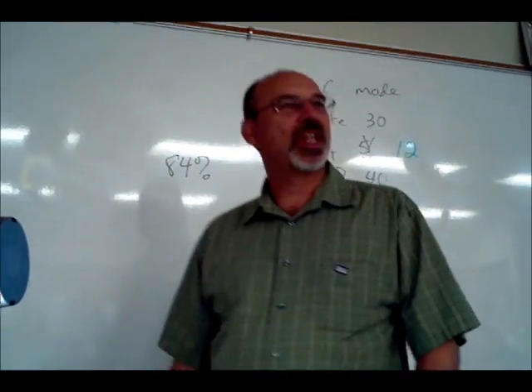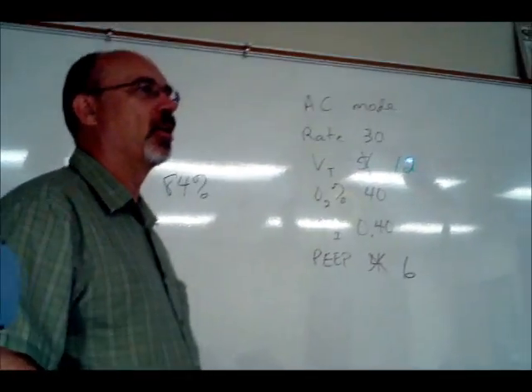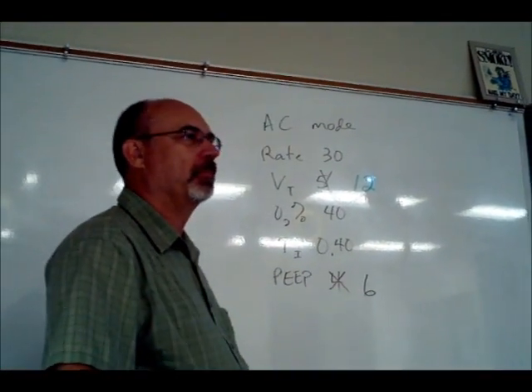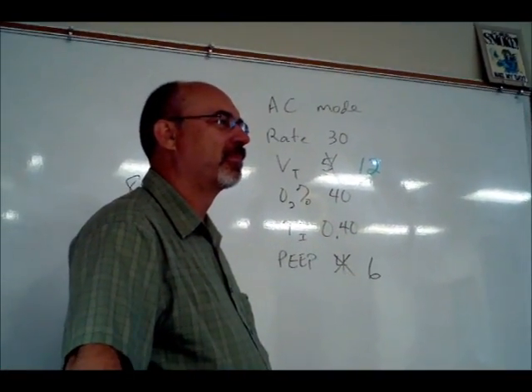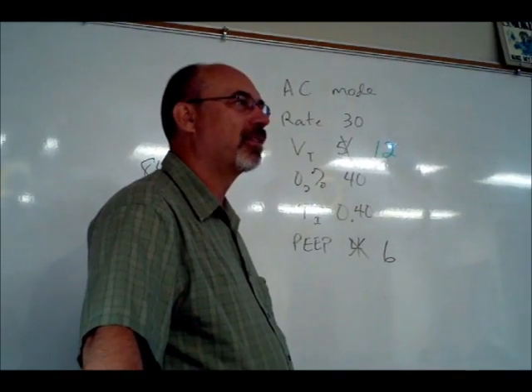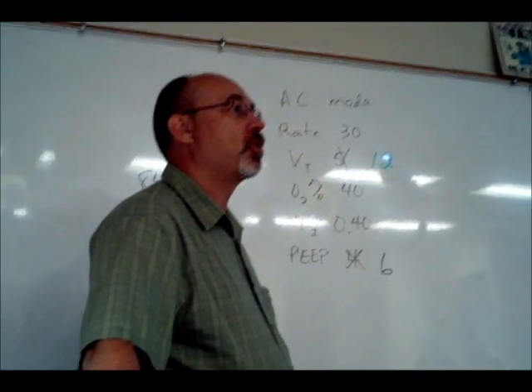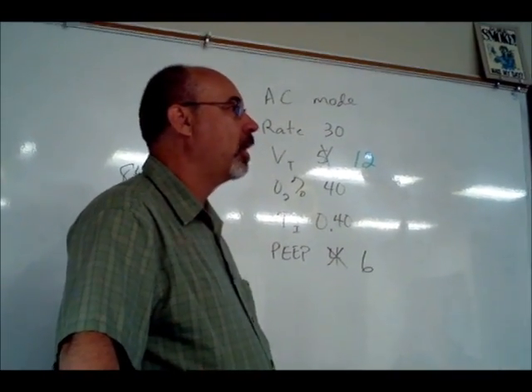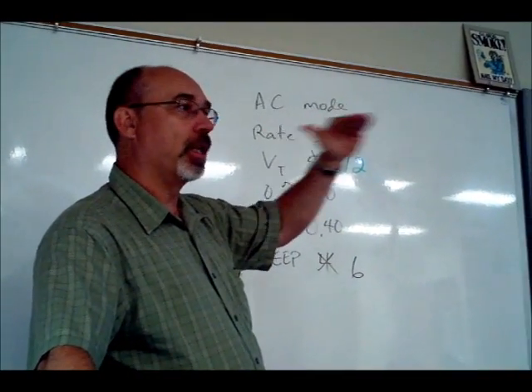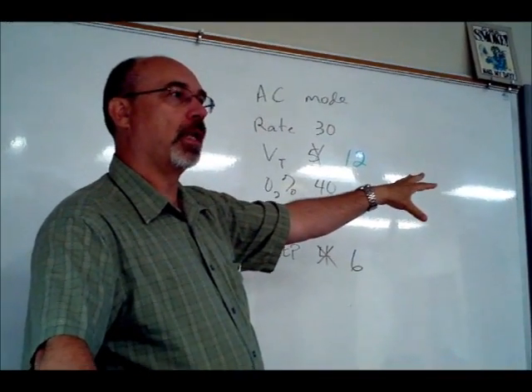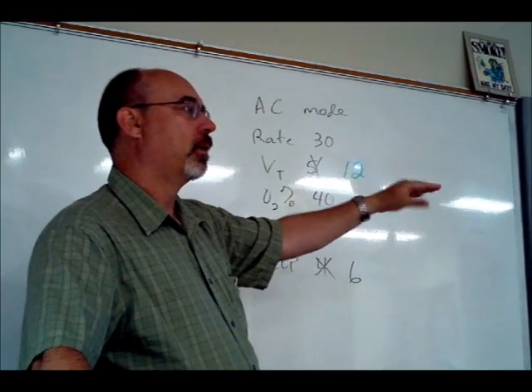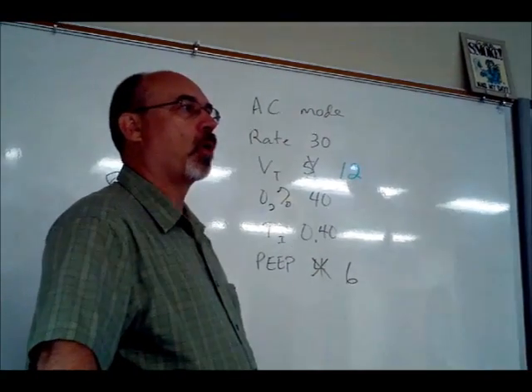Aha! You're anticipating my next question. What's going to change now on this ventilator when I increase my PEEP? Well, something will change. The main thing that's going to change is your peak airway pressure, okay? Because we're up in our baseline. It's still going to try to put in the 12 because that's what we're telling it to do, okay? But it's going to take a little bit more pressure.